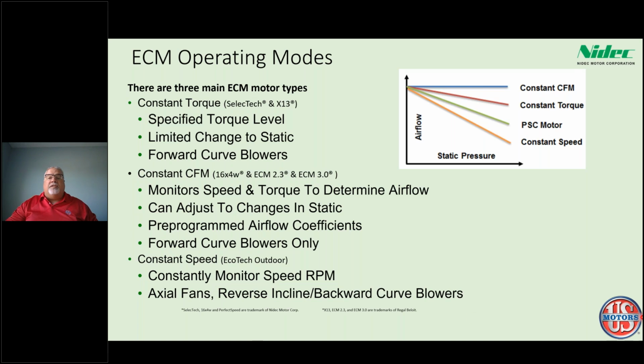As static pressure increases, and I've got a chart here, all of these motor types are all starting out at the same level. As static pressure increases, a constant torque motor, because it doesn't know where to go to continue that constant CFM, does drop off a little bit as you continue to increase static pressure. Obviously it's not as significant as a PSC, or constant speed motor. PSC, or permanent split capacitor motors, have really been the workhorse for the HVAC industry for years. You can see one of the main reasons we've gone to the ECM is they do a better job of holding that airflow.